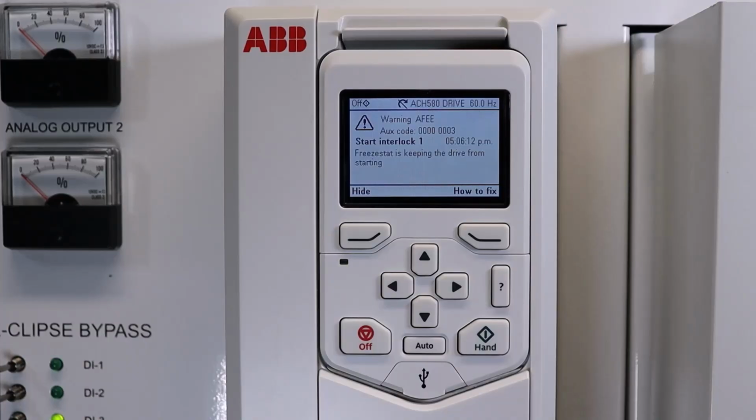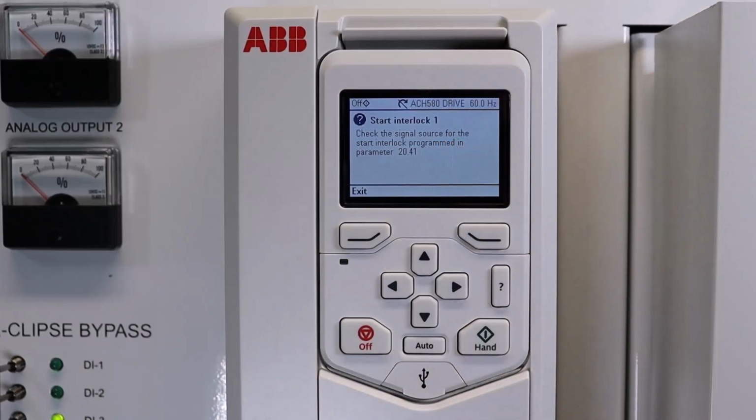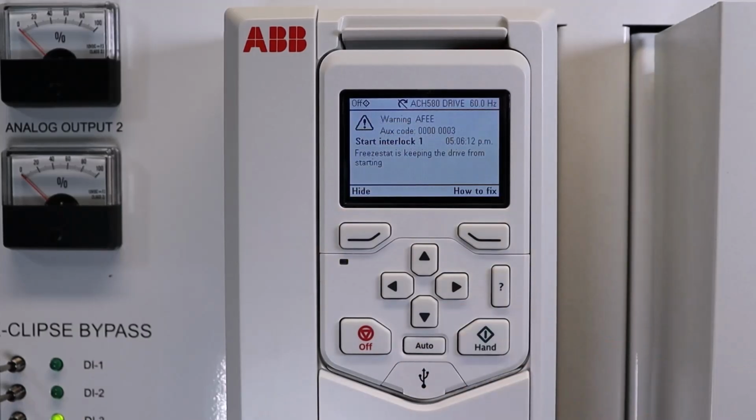So let's say you're at the customer site and you come up to a drive and it has this start interlock fault already. The customer is saying, we already checked it and the freezestat's perfectly fine, it shouldn't be doing this. You can go in the how to fix and it's saying, check the signal source for the start interlock programming and parameter 20.41.